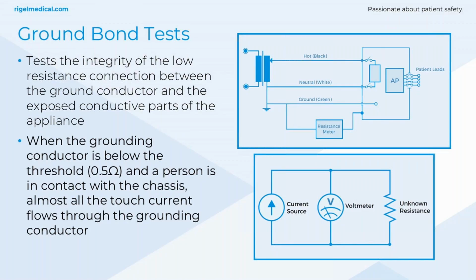So ground bond tests. We know that class 1 equipment has a ground conductor, so leakage current on the chassis or enclosure can flow to ground, and that helps to prevent any harm to anyone. It's a proven safety measure for preventing electrical shock, although we're moving more towards class 2 devices now that don't have this feature. But it is a means for many medical devices of preventing that electrical hazard. So what we're doing is we're measuring and checking the resistance between the appliance and ground, and that ensures that the safety measure continues to work throughout the medical device's lifespan. So we're still making sure that that integrity remains.